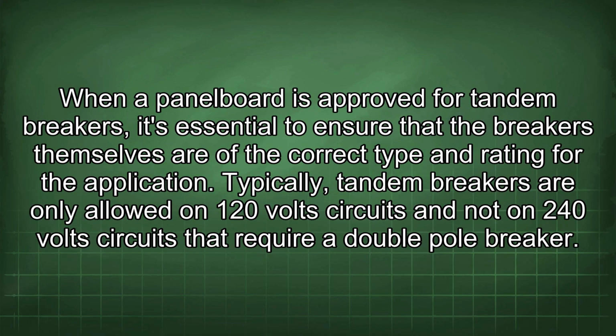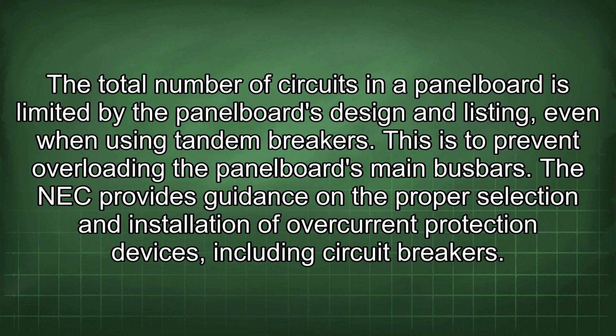When a panel board is approved for tandem breakers, it's essential to ensure that the breakers themselves are of the correct type and rating for the application. Typically, tandem breakers are only allowed on 120-volt circuits and not on 240-volt circuits that require a double pole breaker. The total number of circuits in a panel board is limited by the panel board's design and listing, even when using tandem breakers. This is to prevent overloading the panel board's main busbars.